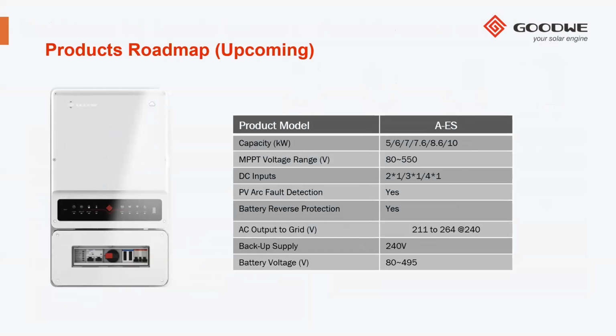Okay, this is just a very brief sneak peek at our hybrid product that we're going to be introducing to market later this year. It's going to be the A-ES inverter, hybrid inverter. Goodwe has had a small gap in our product portfolio. We've been doing very well with our 3.6 and 4.6 kilowatt hybrids, but the gap was between the 5 and the 10 kilowatt single phase hybrid mark. So this product is going to fill that gap. It's going to have multiple MPPT inputs, and it's going to have high voltage battery input, so anywhere from 80 to 490 volts. And that should be introduced in the second half of this year.